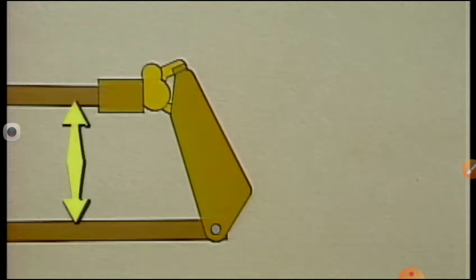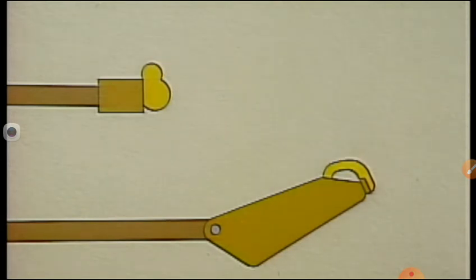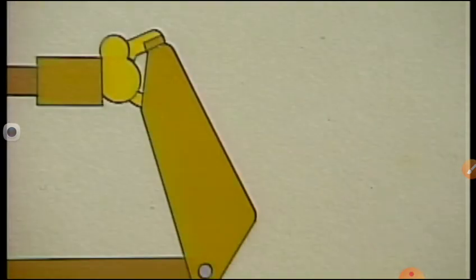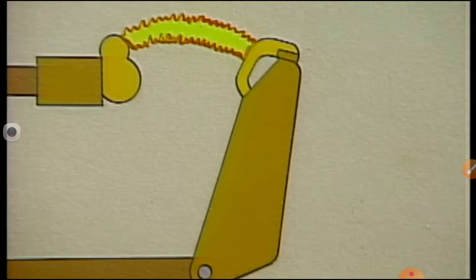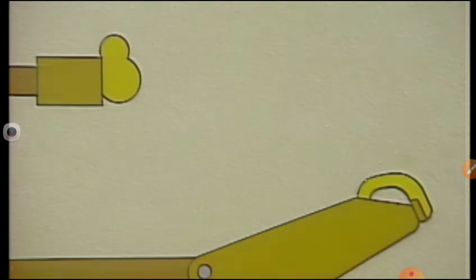The illustration includes two conductors connected by contacts to make a circuit. To break the circuit, the speed at which the contacts separate is important, because the faster the contacts open, the less time there is for an arc to form and maintain itself. When the contacts separate rapidly, there is little time for the space between the contacts to heat up and become a conductor. Distance between the contacts is also important. As the distance increases, the arc has to stretch in order to maintain current flow. The greater the distance, the more voltage is needed to sustain current flow, and eventually the arc will extinguish.